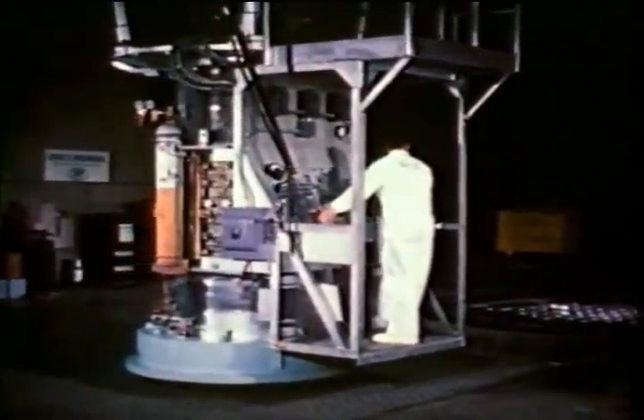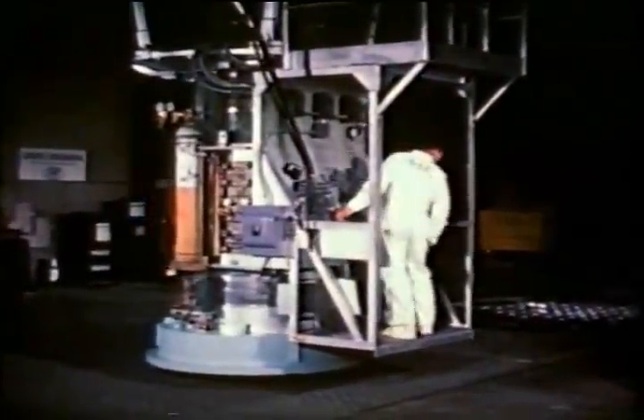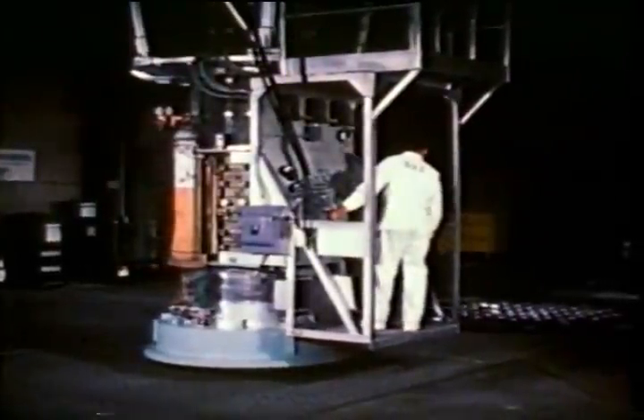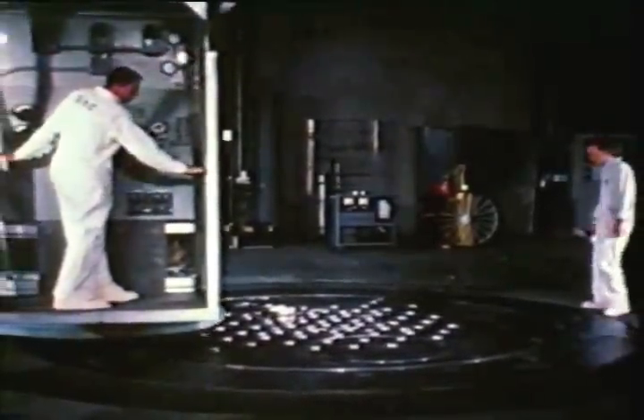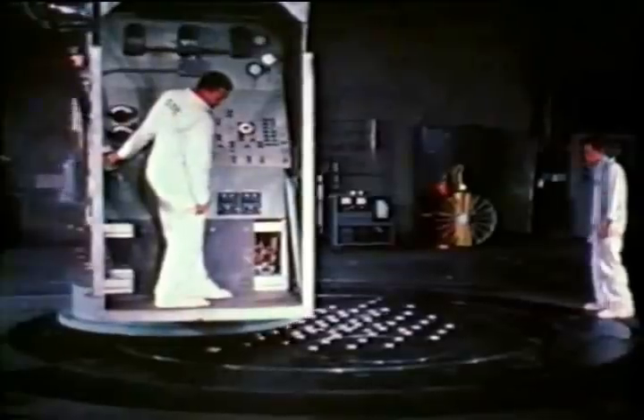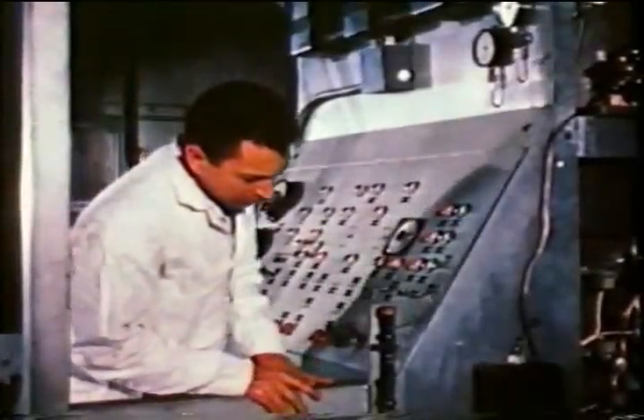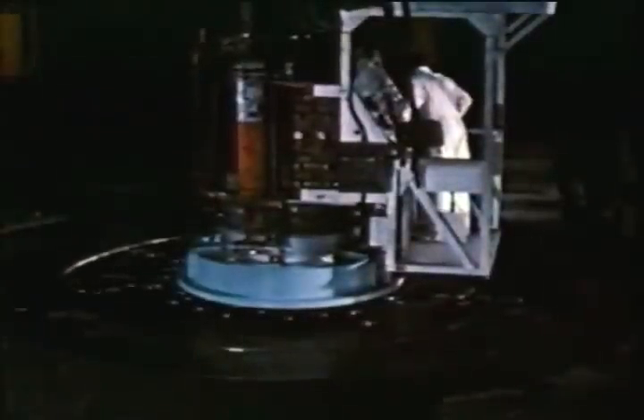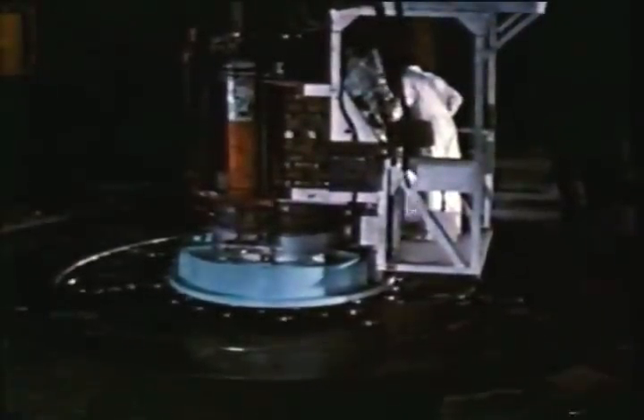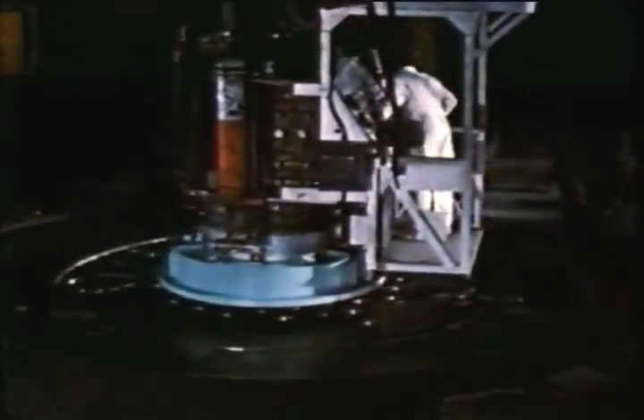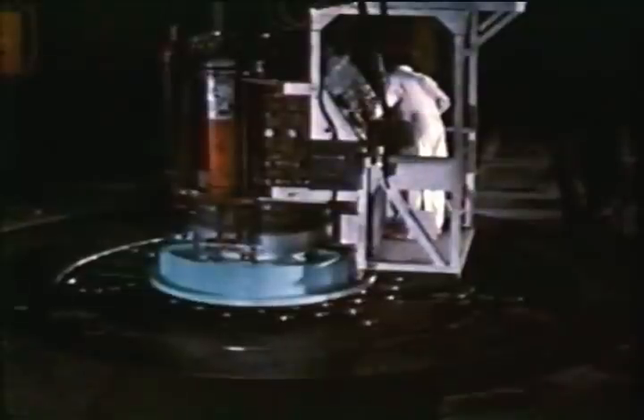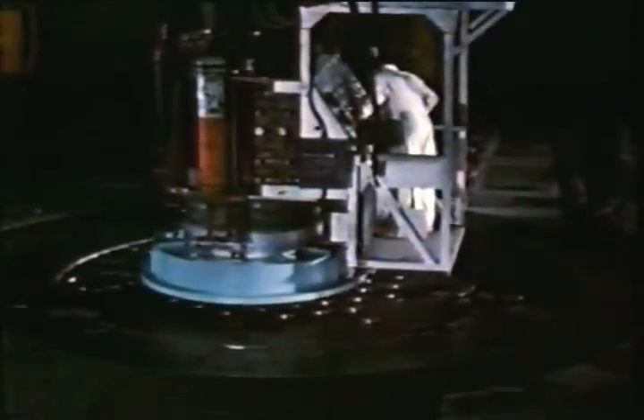Because the fuel elements become highly radioactive from reactor operation, used fuel elements are removed from the core by a shielded fuel handling cask. This 34-foot high chamber is suspended from a bridge crane. It is shielded by 35 tons of lead. A central tube, the length of the cask, accommodates 2 fuel elements.